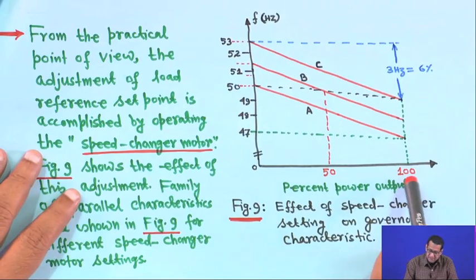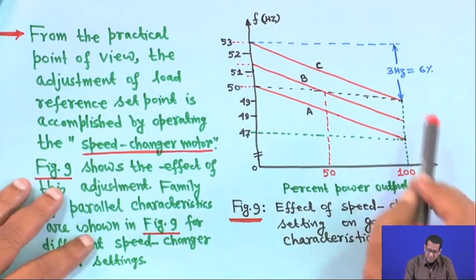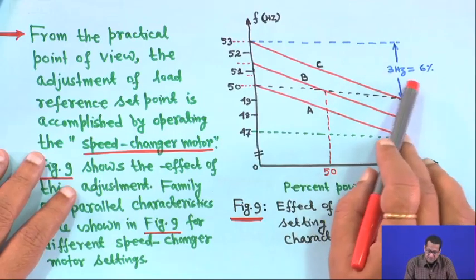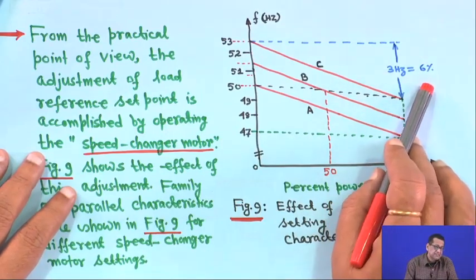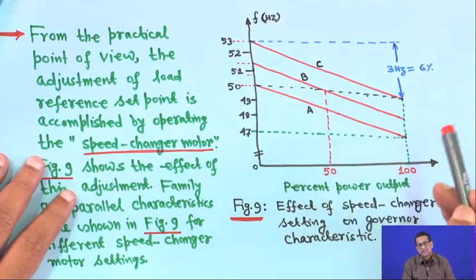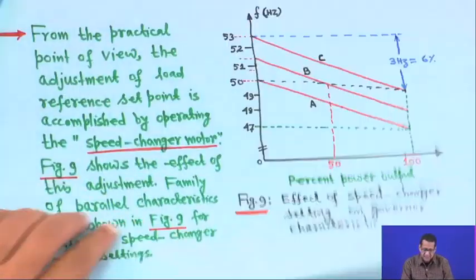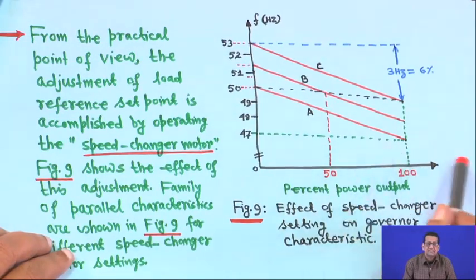With a 6 percent droop setting, a 100 percent change in power output corresponds to 3 hertz in a 50 hertz system. If it is 4 percent droop, it corresponds to 2 hertz, and so on. That is the idea of the speed droop characteristic.